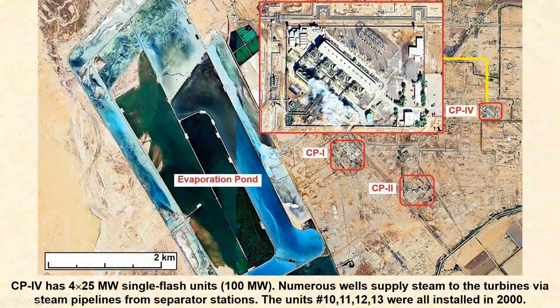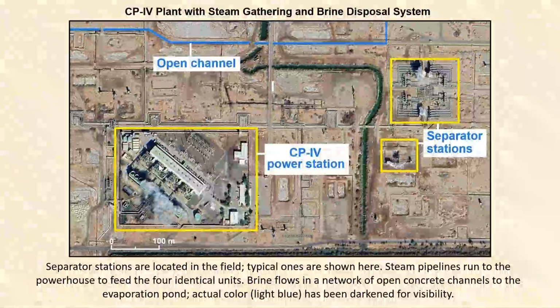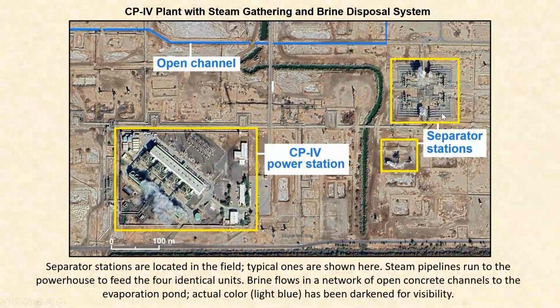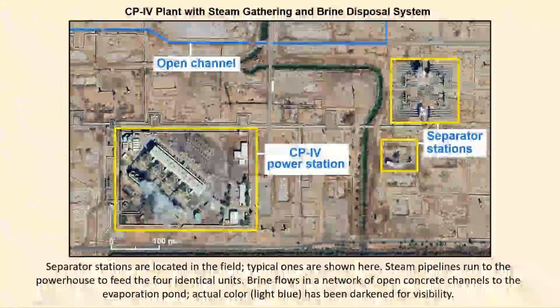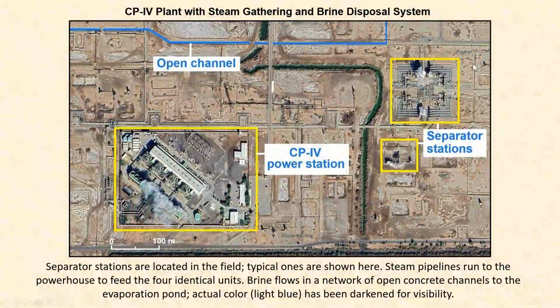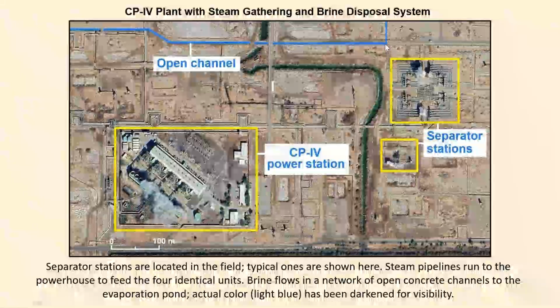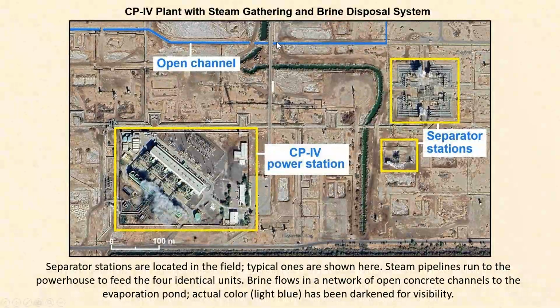Next slide, please. Here's the unit, and here is a typical separator station and a smaller one down here. This is where all the steam gathered from the wells all around this area is brought and separated, and then the steam is brought over to this power plant through the pipelines, as you can see. The liquid from this and other separators, which are off in the distance behind this, up in the northern section, is discharged into an open concrete canal, which runs to the west and goes into the evaporation pond.